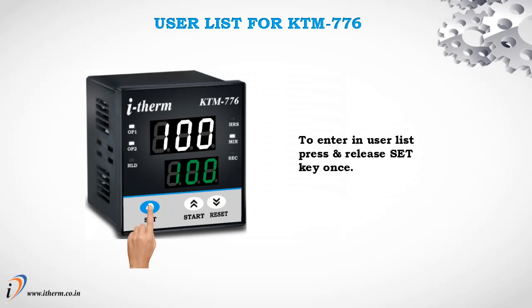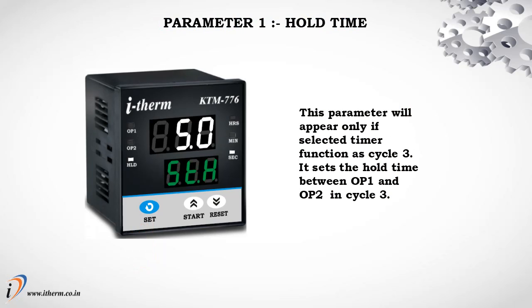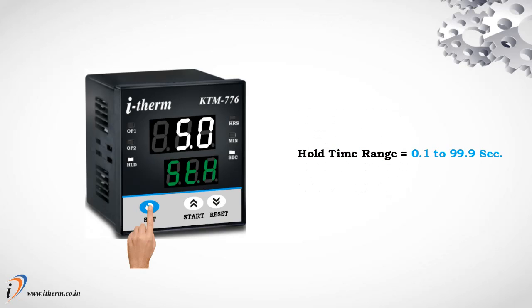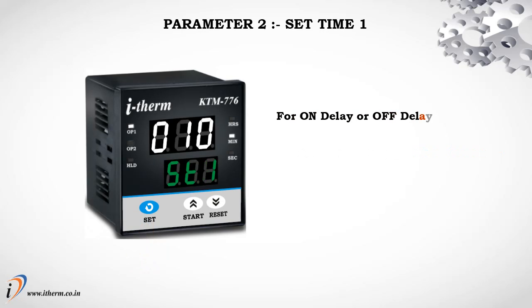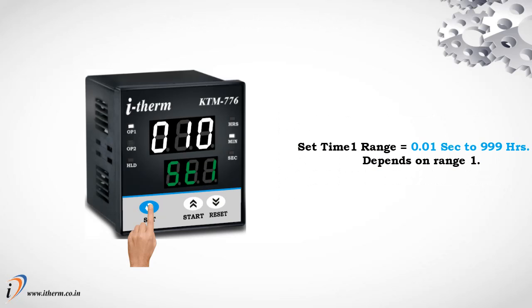User List for KTM 776. To enter the User List, press and release the Set key once. Parameter 1: Hold Time — appears only if timer function is Cycle 3. It sets the hold time between Output 1 and Output 2 in Cycle 3. Range: 0.1 to 99.9 seconds. Parameter 2: Set Time 1 — for On Delay or Off Delay, sets the time for Output 1. For Cycle 1, sets the Off Time; for Cycle 2, sets the On Time; for Cycle 3, sets the Forward Time for Output 1. Range: 0.01 seconds to 999 hours, depending on Range 1.